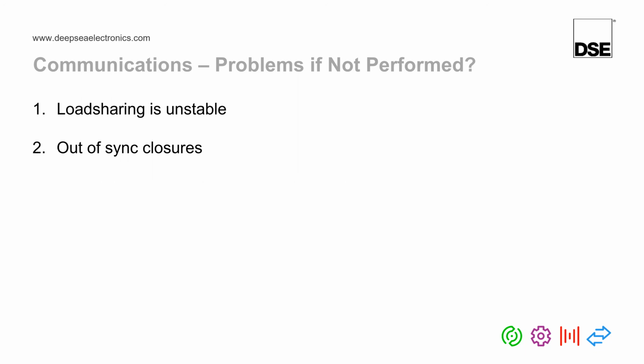On top of that, we also have a feature whereby if the MSC link completely fails, so for example MSC1 and MSC2 fail, you can actually revert to a droop form of load sharing. Droop form of load sharing basically means that the modules will carry on load sharing. However, the frequency and voltage will not be maintained at nominal, but that is just a function of droop. So at least there are redundancies built into the DeepSea module if you choose to enable them and wire them in case of MSC failures.